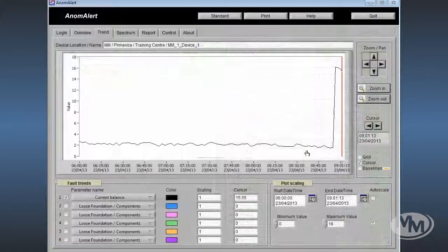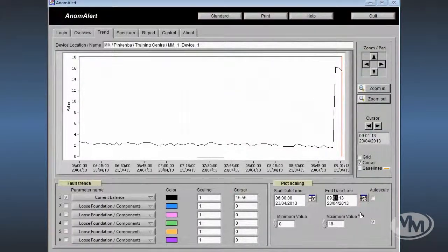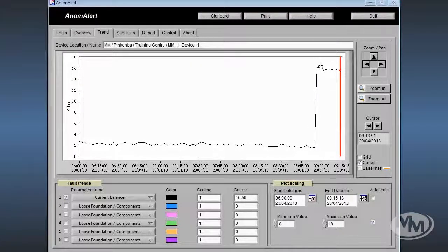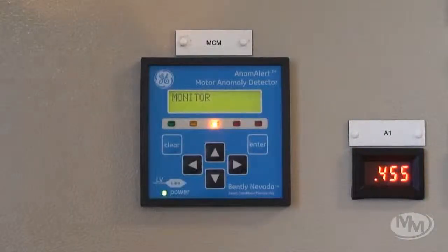From this page, the trending for the appropriate alarms can be directly accessed. By double clicking on the watch criteria, it takes us to a trending page showing the current balance values. It can be seen that by introducing the fault on the machine, we have caused a large rise in the current imbalance. This has been detected by the Anomalert unit.